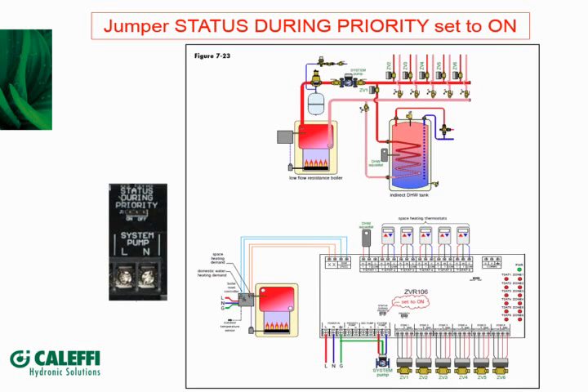We're trying to give you the most flexibility as possible without having to, like I said, do jumpers and wire nuts and whatnot. Question, do you need a transformer for each module when you start busting them together, like between the first module and additional expansion modules? Yes. You need power and you need transformers inside of each one of them. So whatever you buy, let's say you go to the distributor and you buy a three-zone valve box and another 3-zone valve box, everything's in there to do it already because the transformers are in there. You just have to bring line, neutral, and ground in to each one of them.